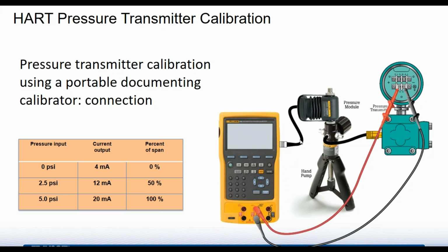In this case, we're hooking up a pressure module, and we've connected it right up to the pump, so it's just a straight shot. But in many cases, you're going to have the pressure module hanging separately close to the transmitter, and in that case, you're going to have another pressure line going to the pump. So you may have a T involved, and more pressure lines you have to deal with, and of course, with pressure lines there's always a chance of leaks. You always have to get your thread seal tape on there and make sure you've got a good connection. From that point, now you've got your pressure source. You can pump up to the different pressure values, measure your 4 to 20 output, and verify your calibration is in spec.